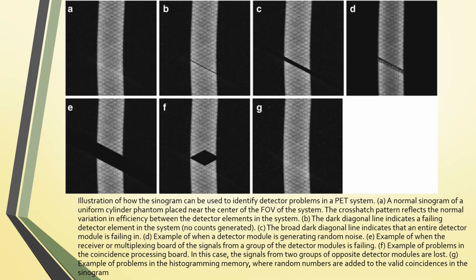This is an illustration of how the sinogram can be used to identify detector problems. In A, you see a normal sinogram. Notice the crosshatch pattern. That reflects the normal variation in efficiency between the detector elements of the system. In B, you have a really thin, dark diagonal line that indicates a failing detector element within the system, where no counts are generated in that line.